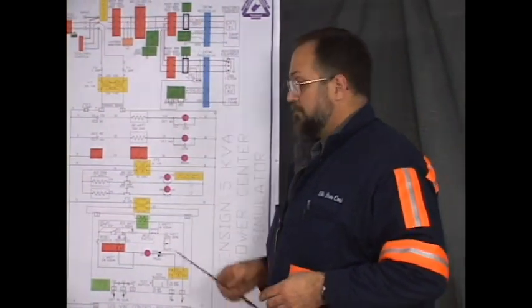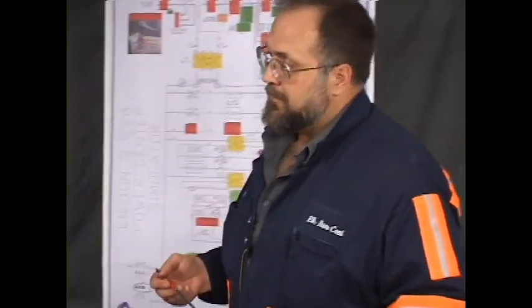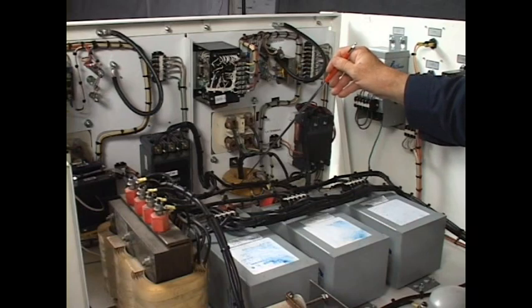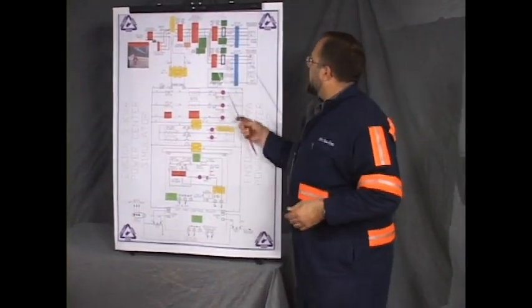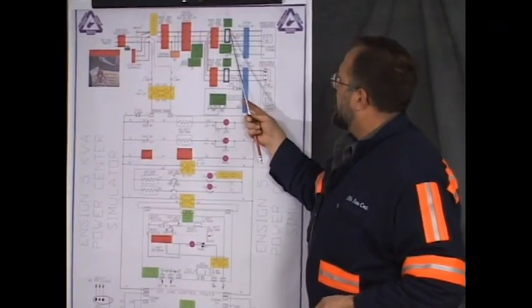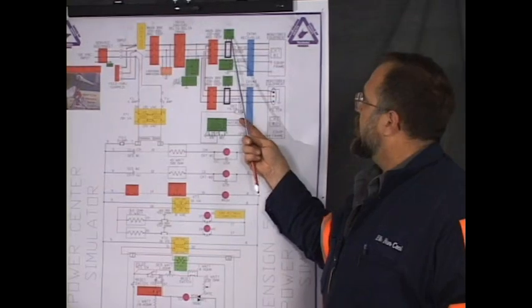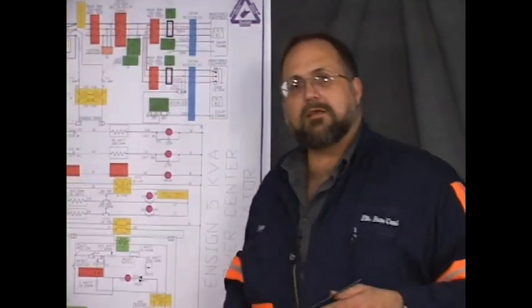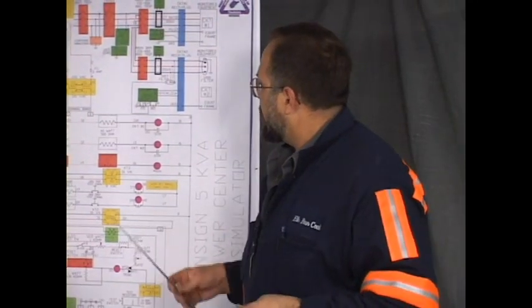That provides the motion. As the current flows up, peaks, down to neutral and then below neutral to a negative peak and then back to neutral, the magnetic field surrounding that conductor expands and contracts in the same manner. And that provides motion. The field is moving. These phase wires that pass through the window of the CT are not directly connected. You can see those here on the CT. They're not connected electrically, they're not joined mechanically. They're considered to be magnetically coupled. And as the field expands and contracts, it can induce a current in the current transformer that will operate this relay. It will make electricity in a sufficient quantity to power this coil.